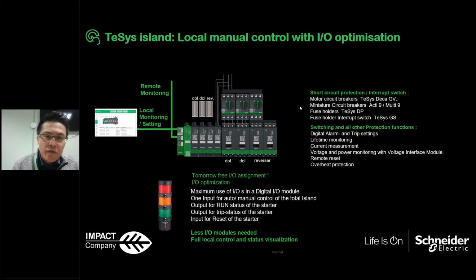And with the system, we also have the I/O modules, so now we have I/O optimization. What it means is that we can utilize these I/O modules to send the signal to a tower light or pilot lights for the on/off of the motors, if you like, on the panel. So you no longer need another I/O module outside the TeSys island and the contactors to send the signal to the signal lights for the on and off status. Now you can use the I/O modules already provided with the TeSys island, and optimize them to control and monitor the status of these contactors.